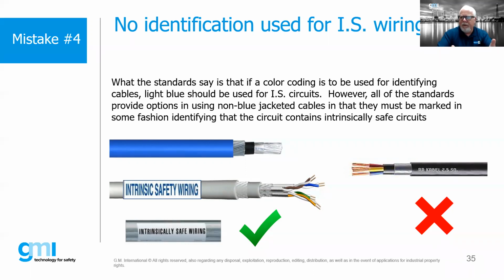However, if I see that it's marked intrinsic safety, then there's a possibility that I can use non-certified, non-EX type product. But I have to look at that very closely - that doesn't mean I can use non-EX certified products all the time for intrinsic safety. I'm not saying that. But there is a level of flexibility when we use IS that we can do things we couldn't normally do.